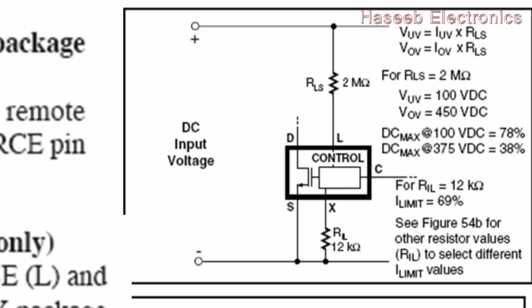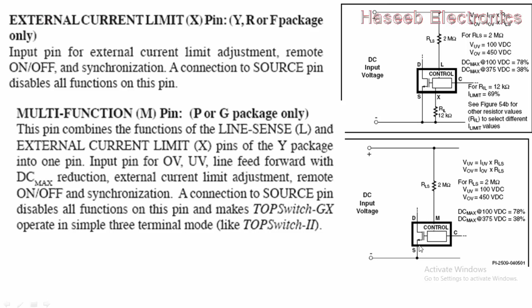This X pin is available in Y, R and F packages. Then there is the M pin, multifunction pin, which has the same function as the L and X pins combined. This pin combines different functions like line sense and external current limit. External current limit is basically available as a separate pin in Y, R and F packages, but the P and G, 8 pin DIP and 8 pin SMD packages don't have an X pin. So under voltage, over voltage, and current limit are all adjusted from here, and if this pin is connected to ground, it disables all functions and the IC will just start at 132 kilohertz directly.